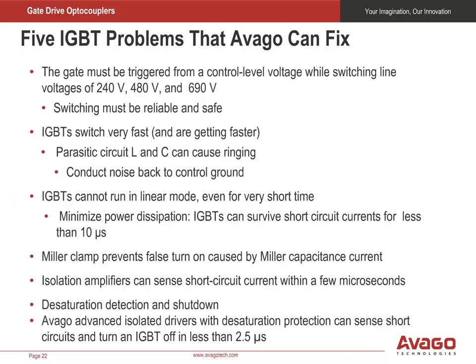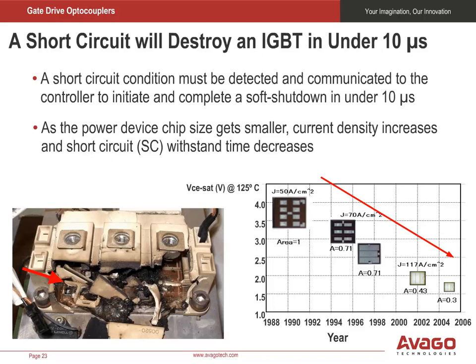Some of our latest isolated gate drivers include a Miller clamp that prevents false turn-on due to the large currents flowing through the IGBT's Miller capacitance. Our isolation amplifiers can sense the short-circuit current and react within a few microseconds. Avago's advanced isolated drivers with desaturation protection can sense short-circuits and turn an IGBT off in less than 2.5 microseconds. Protection circuits must be activated to shut down the power device in under 10 microseconds to prevent switch damage.